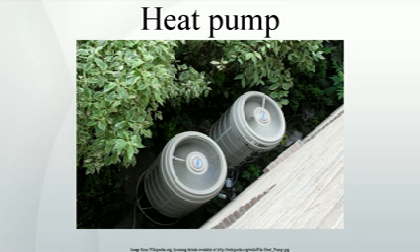The design of the evaporator and condenser heat exchangers is also very important to the overall efficiency of the heat pump. The heat exchange surface areas and the corresponding temperature differential, between the refrigerant and the airstream, directly affect the operating pressures and hence the work the compressor has to do in order to provide the same heating or cooling effect. Generally, the larger the heat exchanger, the lower the temperature differential and the more efficient the system becomes. Heat exchangers are expensive, requiring drilling for some heat pump types or large spaces to be efficient, and the heat pump industry generally competes on price rather than efficiency.